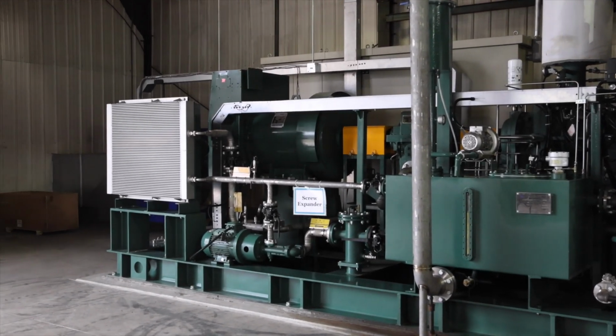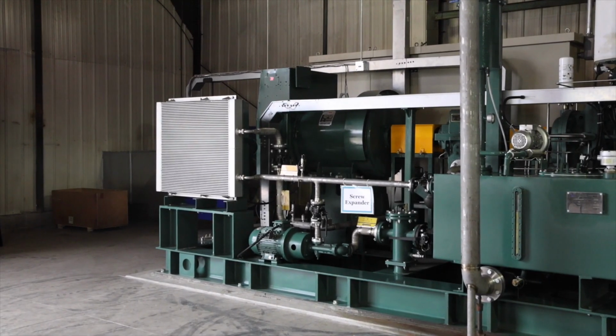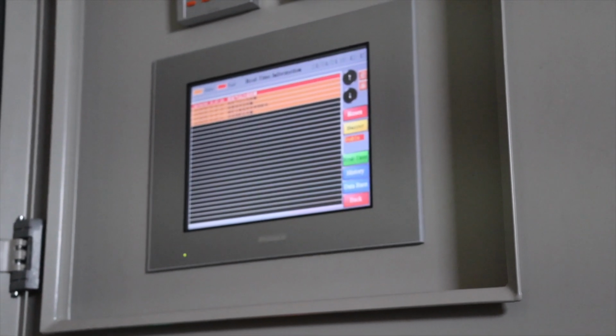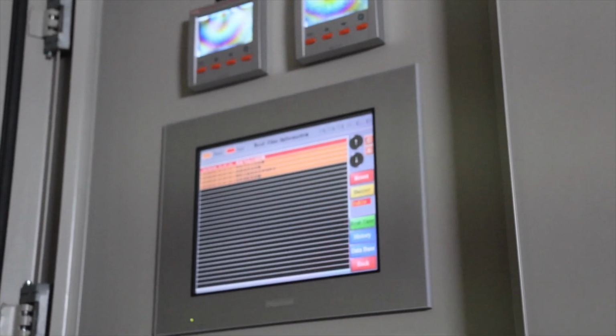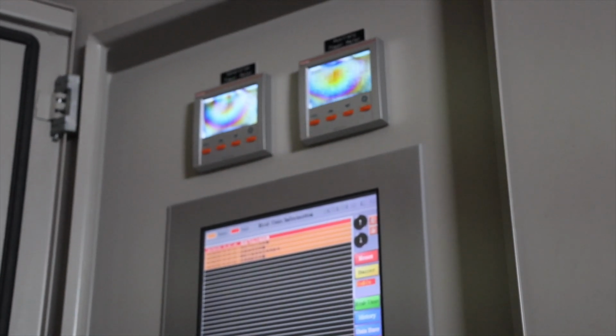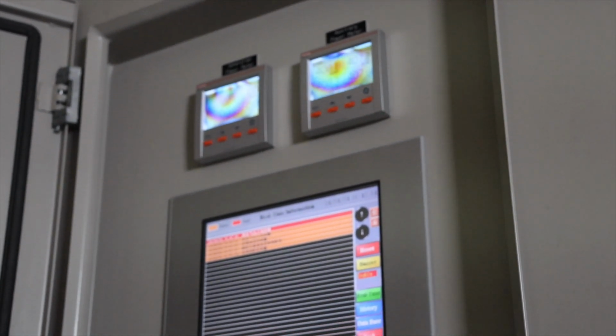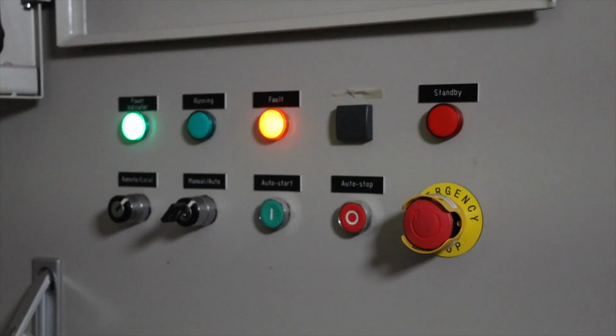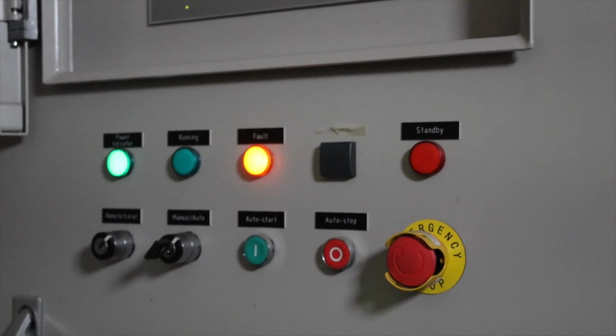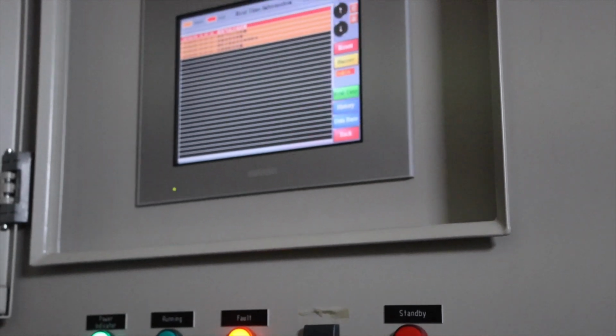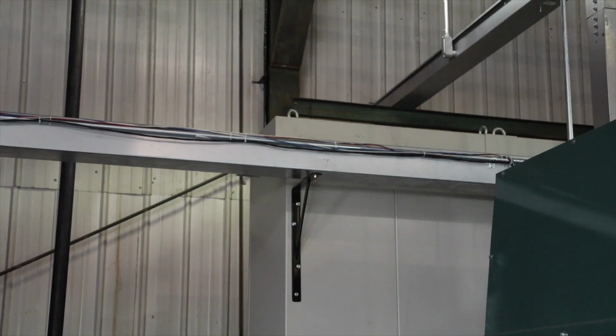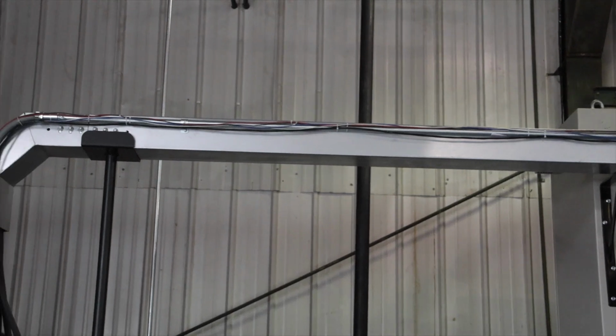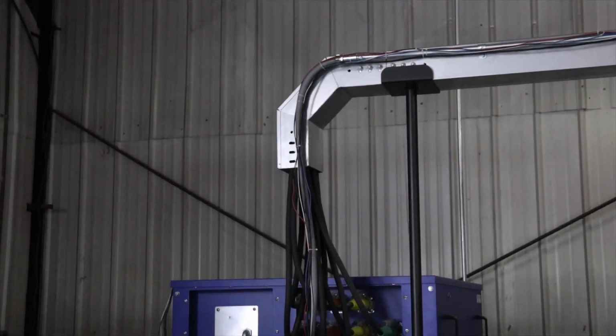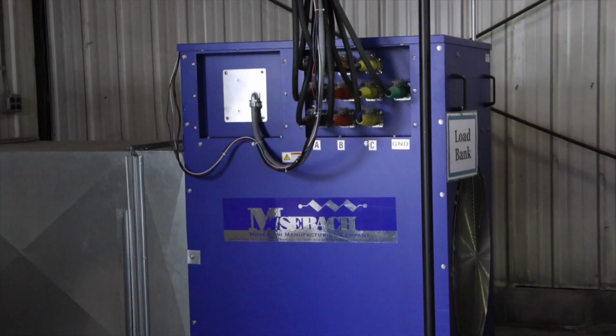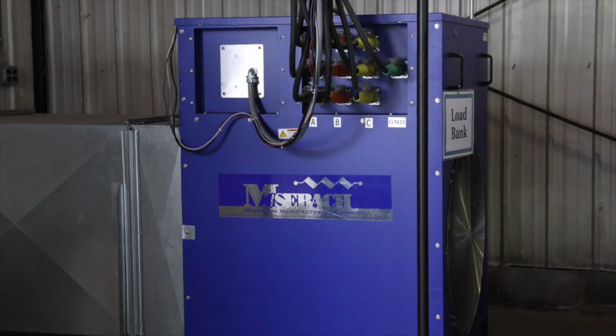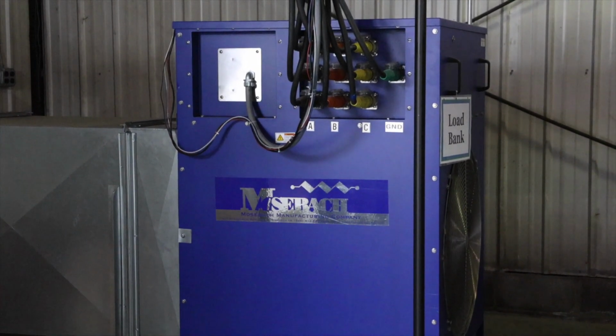The screw expander unit is coupled to a generator by way of a gearbox. In the generator, the electrical power is produced. Electronic equipment in the electrical control panel is used to monitor the manufactured voltage and power. Alarms will notify the operator if the power output falls outside the required parameters. From the control panel, the generated power is fed to a load bank, where it is dissipated for the demonstration model.